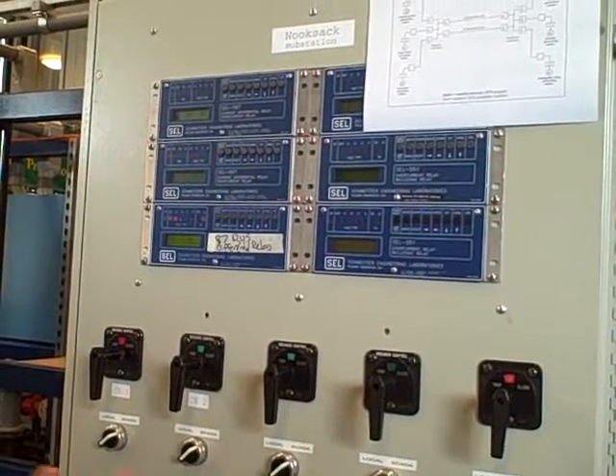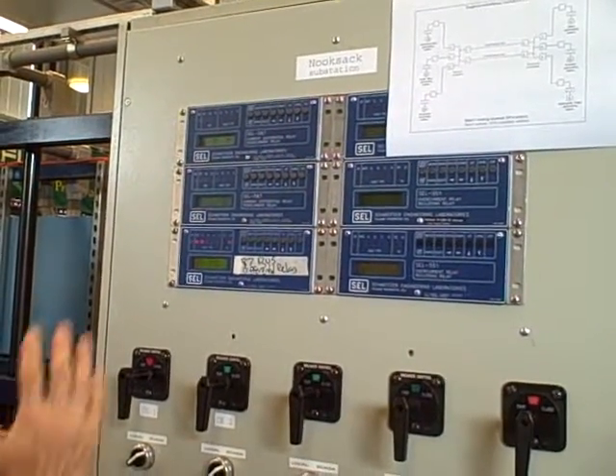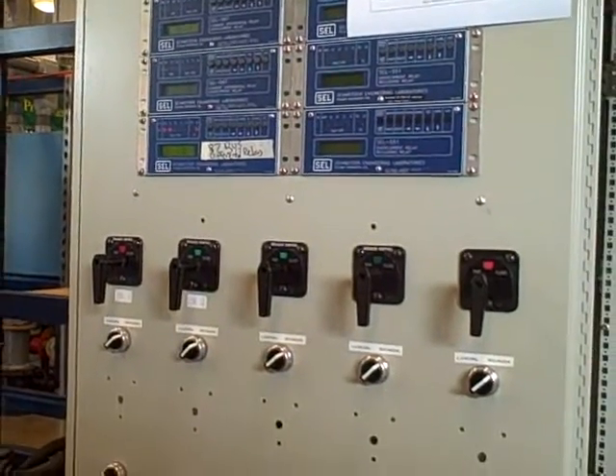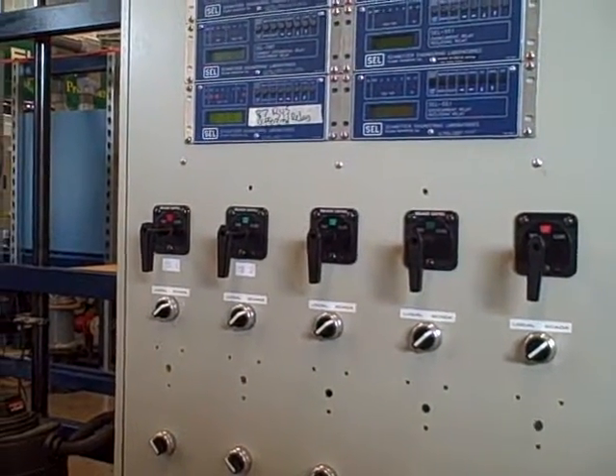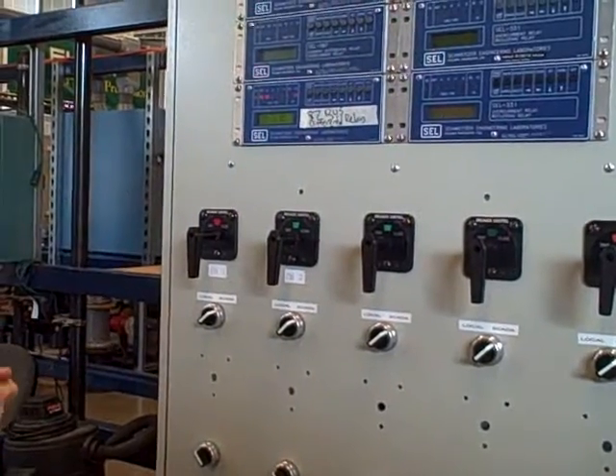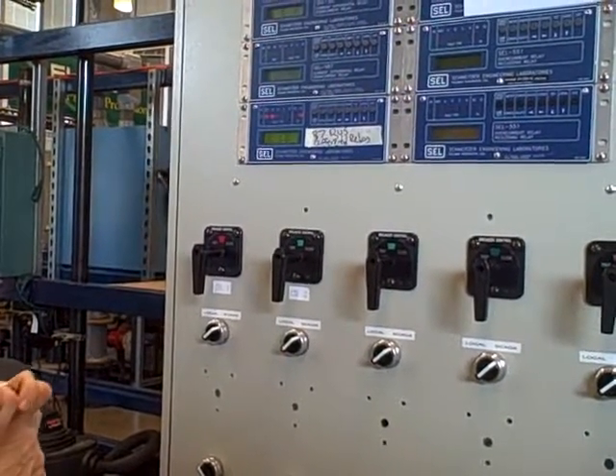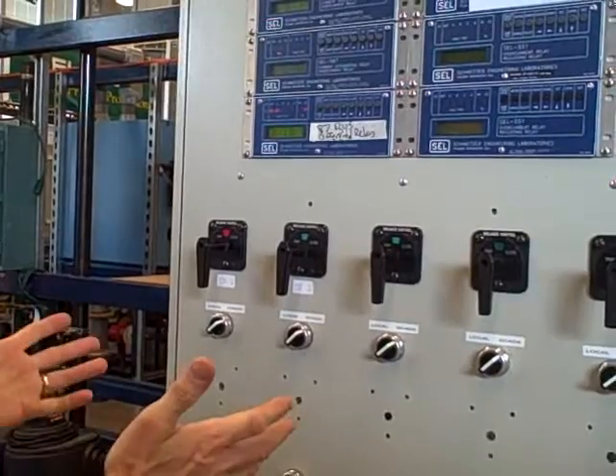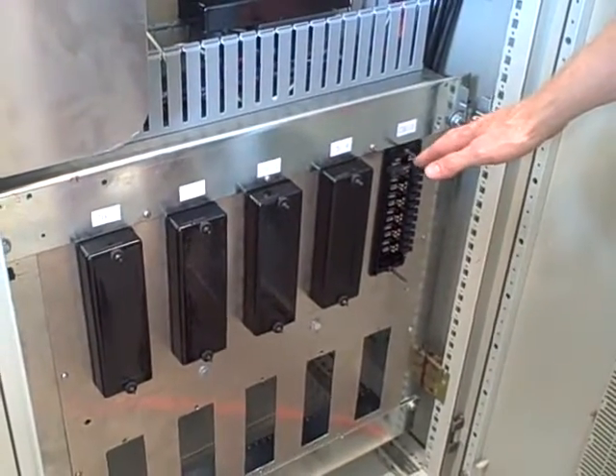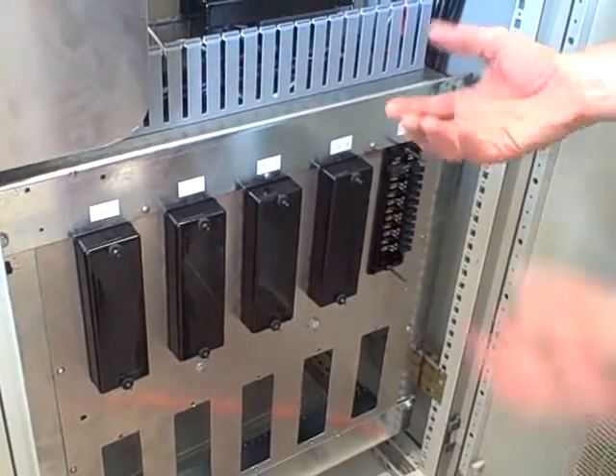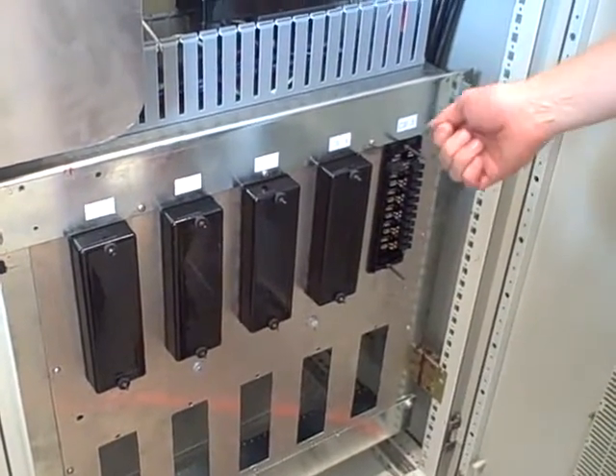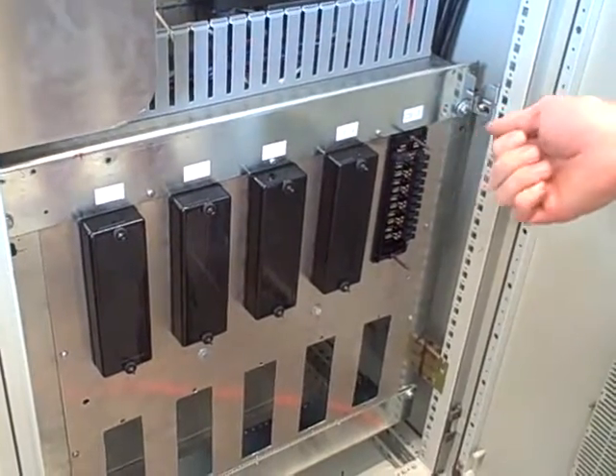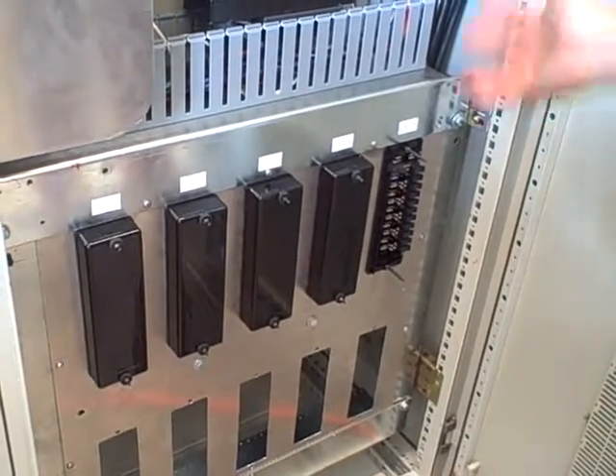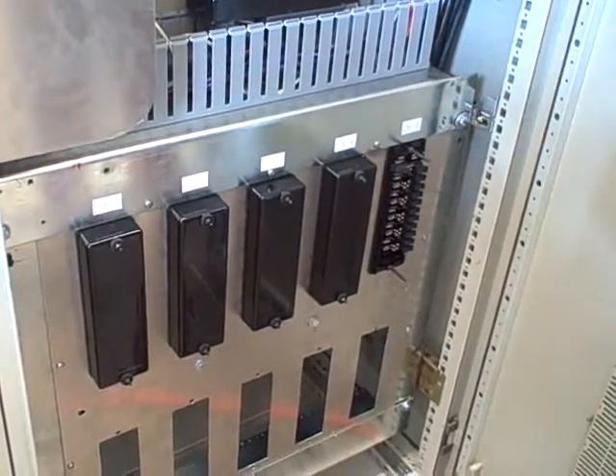Again, there's no actual fault on the bus, but we simulated one just by fooling the relay by opening up one of the test switches in the CT circuit. This is a demonstration of how an 87 bus differential protection works, but also a cautionary illustration for anyone working on systems like this: you had better understand what you are doing when you play around with CT test switches. Although there was nothing unsafe about doing this in terms of our personal safety, we weren't in any danger because this is a self-shorting, make-before-break switch, that would keep the CT shorted as we opened up the rest of the circuit.